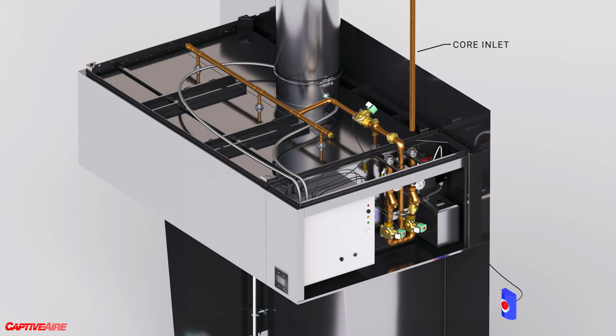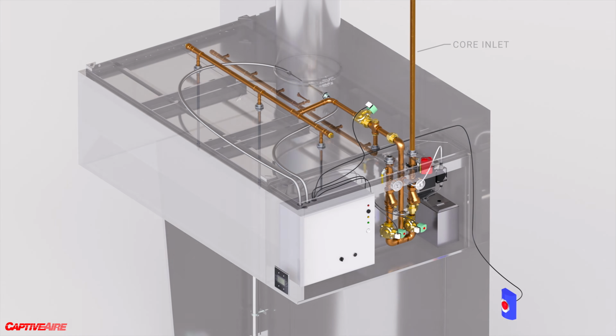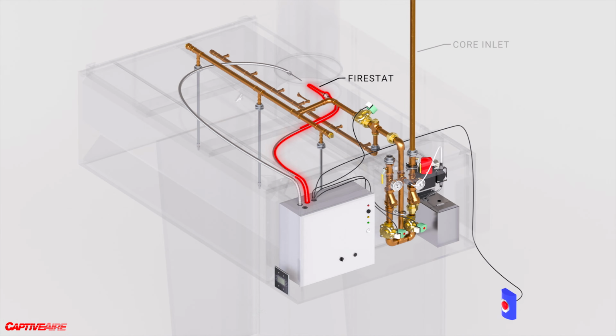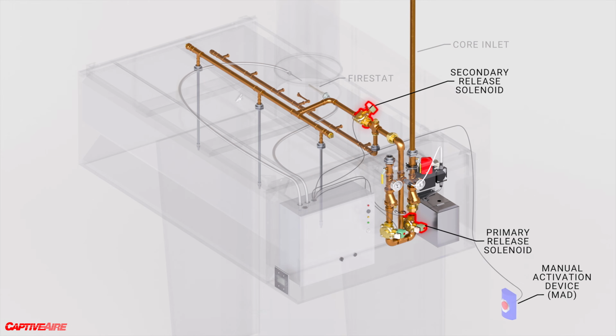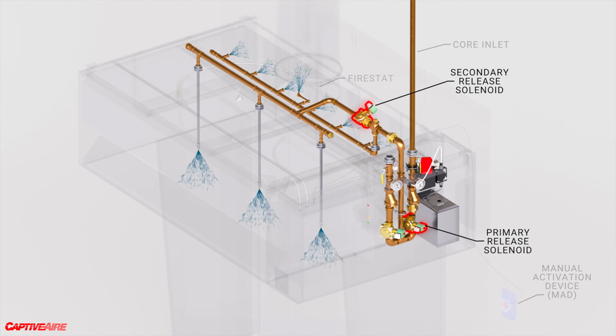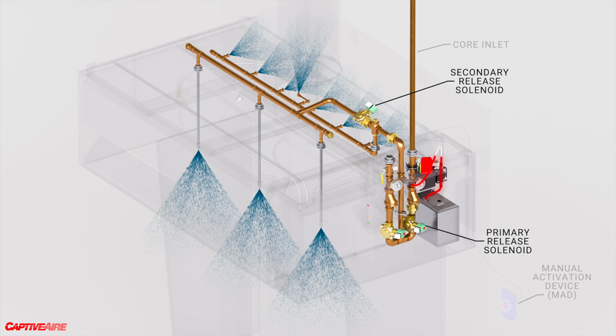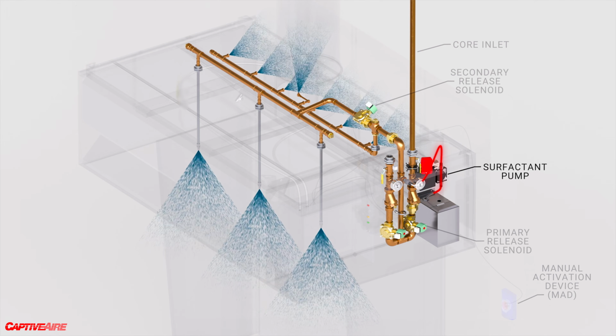With Core, the manifold is connected to the building's water supply or to its sprinkler system. System activation can happen automatically through the firestat's electronic detection, as well as manually by the use of a push button, also referred to as a manual activation device, or MAD. Once activated, two solenoids open, allowing the flow of water and surfactant. The surfactant is injected right here through a specialized pump.